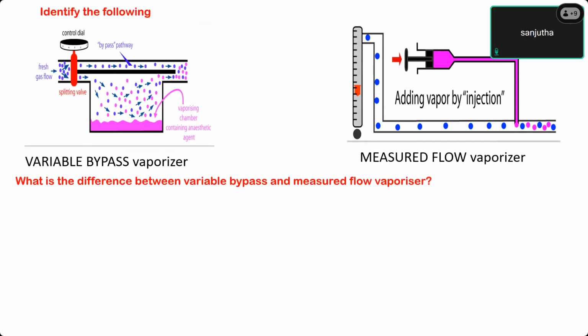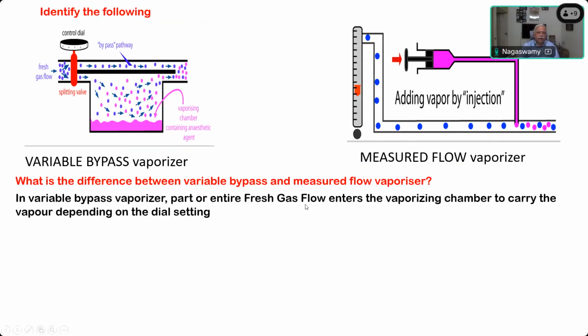All the fresh gas flow will go to the vaporizer, but in measured flow, all the fresh gas flow does not flow through the vaporizer. In variable bypass, some of them will flow into the vaporizer and some will bypass the vaporizing chamber. The vaporizer gases and diluent gases are moving separately. Correct. So in variable bypass, part or entire fresh gas flow enters the vaporizing chamber, called the vaporizing chamber, to carry the vapor depending on the dial setting. You can see the example here. Part of the gas goes without entering the chamber, part of it comes into that, and finally both meet at the other end and go into the patient.